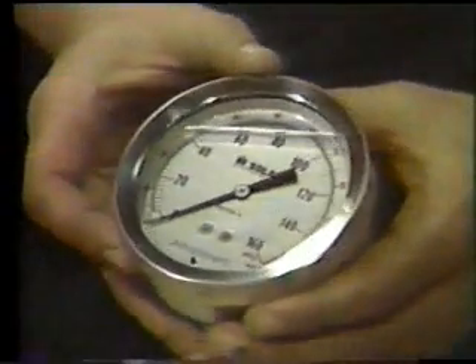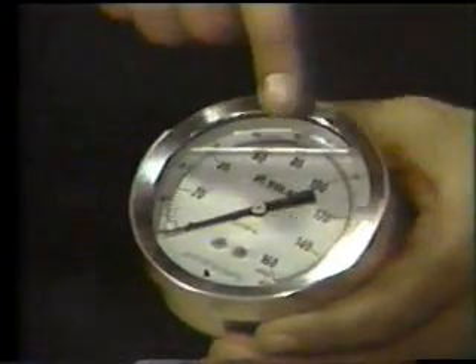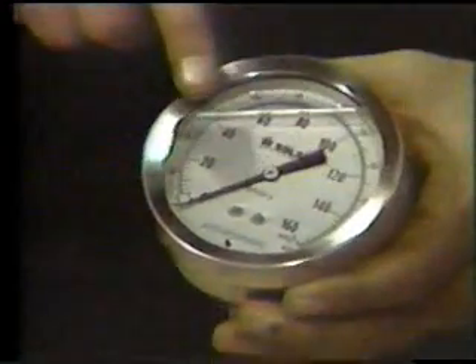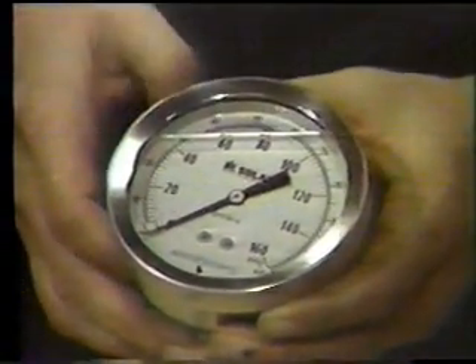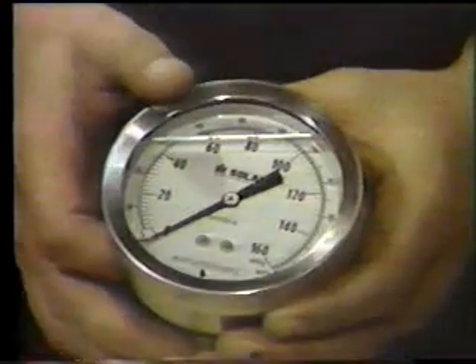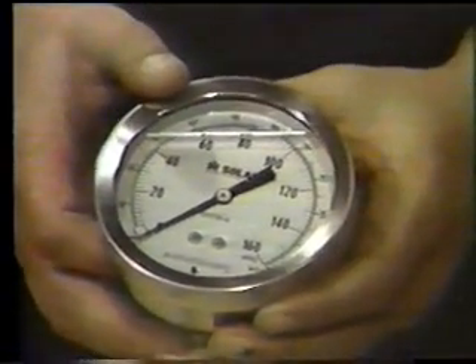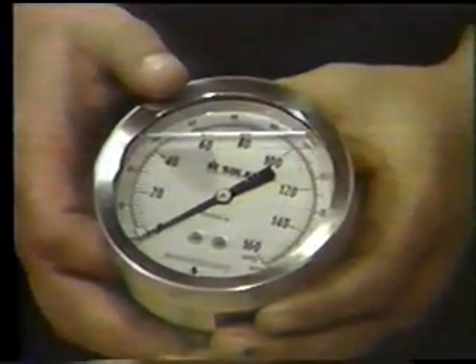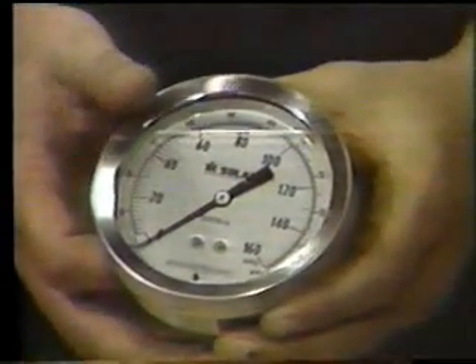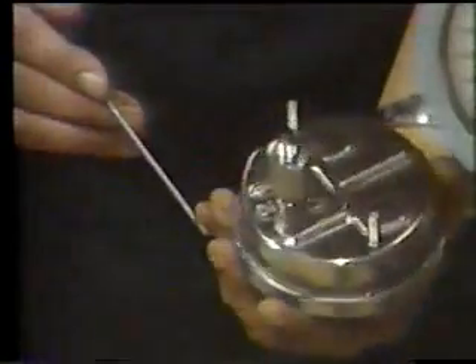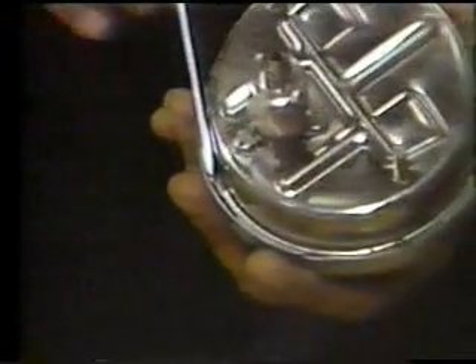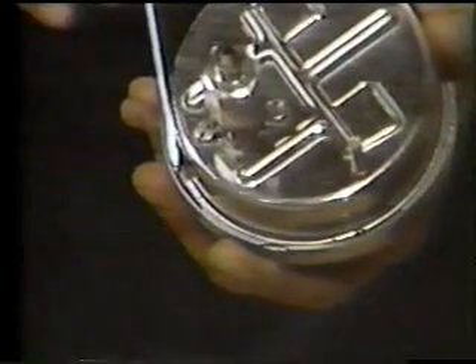Note, liquid-filled gauges should not be disassembled for field calibration. These gauges should be calibrated in an instrument shop capable of replacing the O-rings and gauge fluid. If the gauge is field disassembled and the cover O-ring seal damaged, oil leakage will occur, and the life expectancy of the gauge will be seriously shortened.